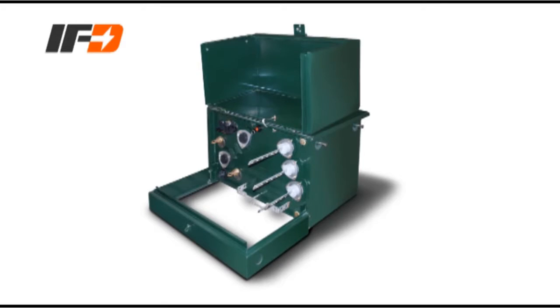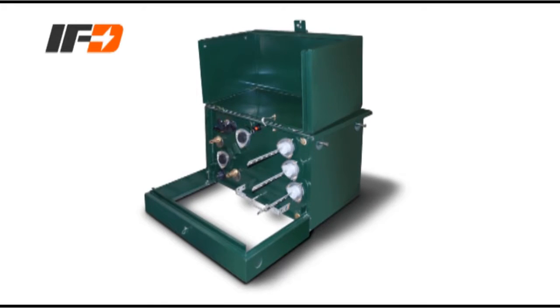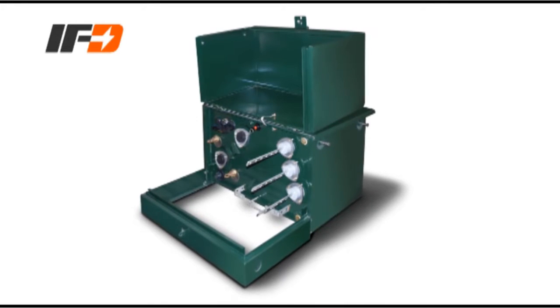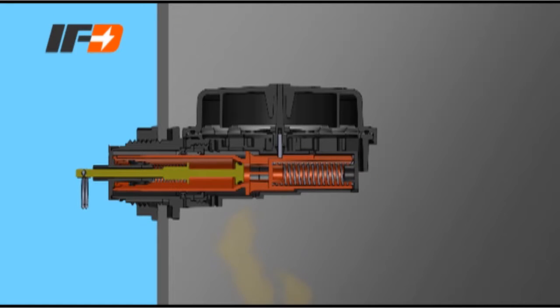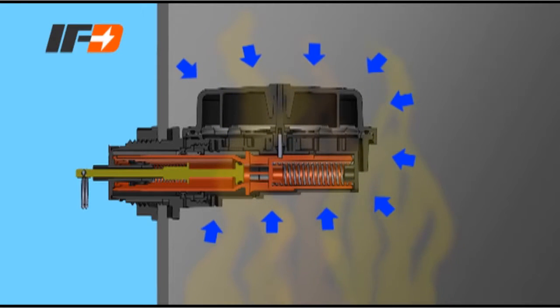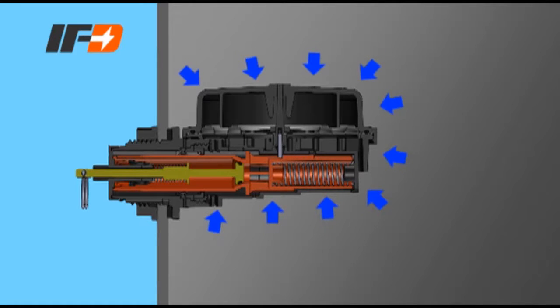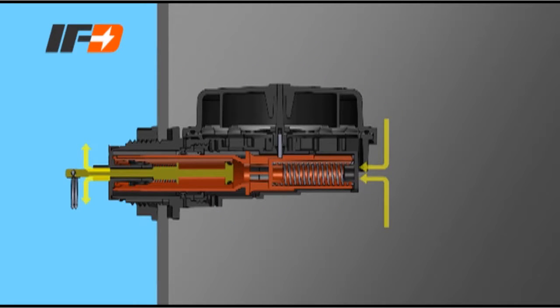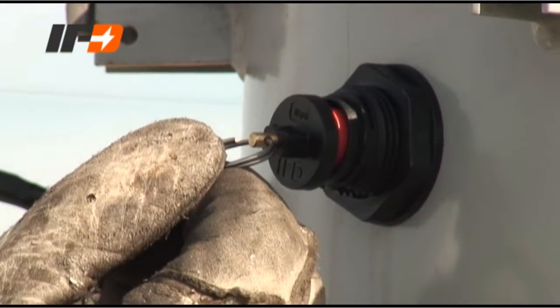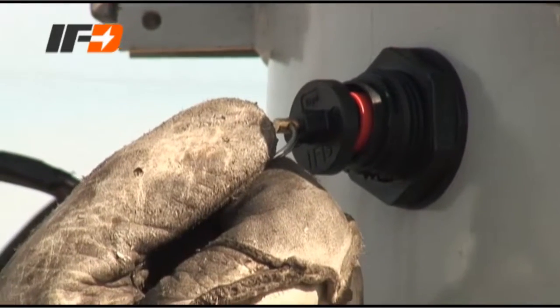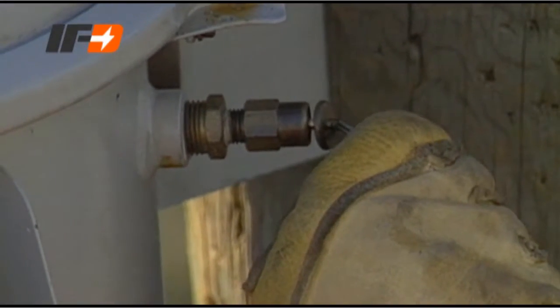The IFD serves a dual purpose, as a fault detector and as a pressure relief valve, or PRV. During hot days or heavy loads, the transformer will heat up and the pressure inside the transformer tank will gradually increase. If the pressure inside the transformer reaches the PRV activation level, the PRV opens, allowing air to escape. It closes when the pressure is reduced. The IFD PRV can also be operated manually, just like other transformer pressure relief valves.